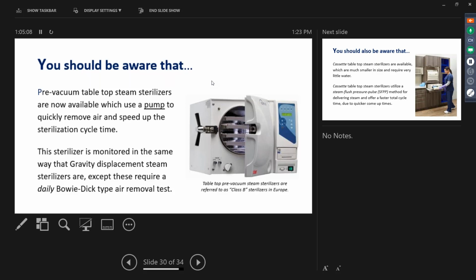It's the opposite of the clinic. They only have gravity sterilizers, and they have to look at a single IFU to see if it's gravity or pre-vac. Guess what? If it comes from Europe, do you think the instruments are validated for gravity? Oh no, because they're not even allowed to use gravity in Europe, so they only come in with a pre-vac setting in a gravity environment.